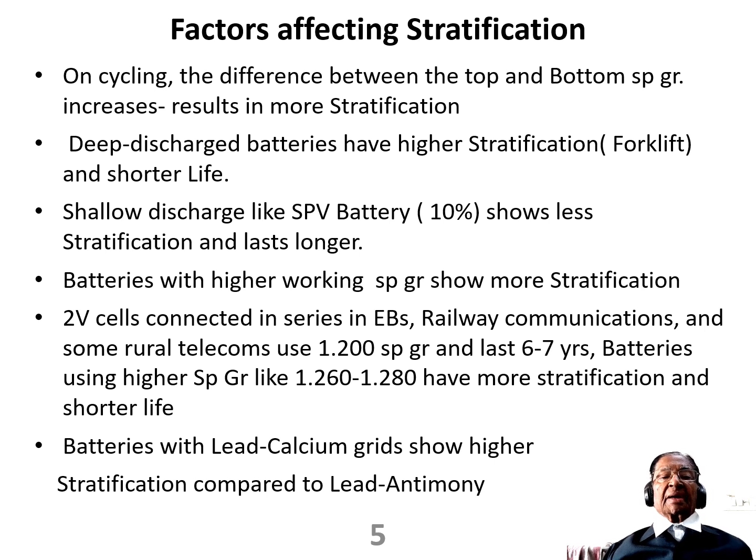Now, deep discharge batteries have higher stratification. For example, a forklift battery, which is deep discharge, shows a higher stratification. A shallow discharge battery like the SPV, solar photovoltaic applications, which discharge only about 10% of the capacity, shows less stratification, and because of that, it lasts longer.